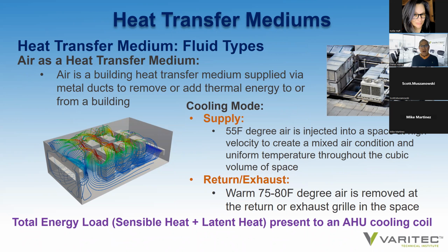Air is supplied as a heat transfer medium through a web of metal ductwork in a building to distribute cool conditioned air to each zone, where that air absorbs the sensible heat energy that becomes present in that space, and it's returned back to an air handler's cooling coil, where that energy is removed and deposited to outdoors.